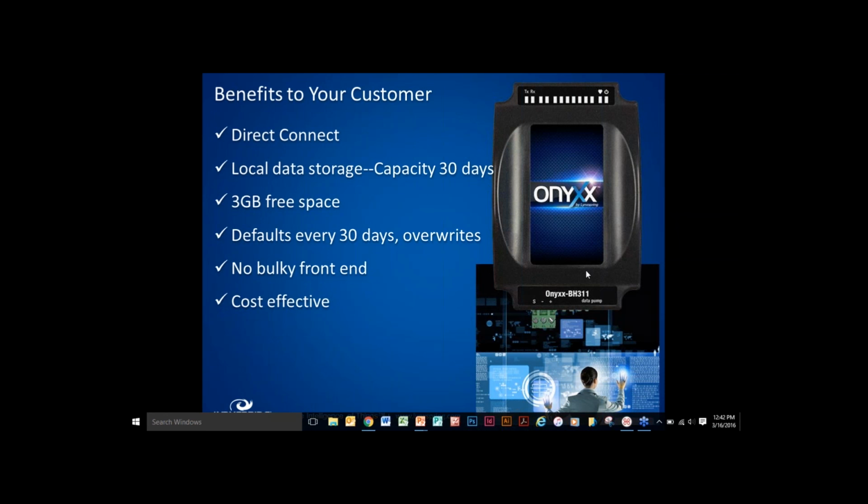I think there was a question earlier. It says how much, if you lost connection, how much data the device buffers. We believe that it easily can buffer up to 30 days worth of data. And then it will push the data again. Obviously, that's dependent on how many points you have in your system, though. So if you're pushing the limits and getting 8,000 points in there, you're probably looking at more like 15, 20 days. But normal system, we consider normal to be probably 2,500 points. You should be safe for 30 days easily.